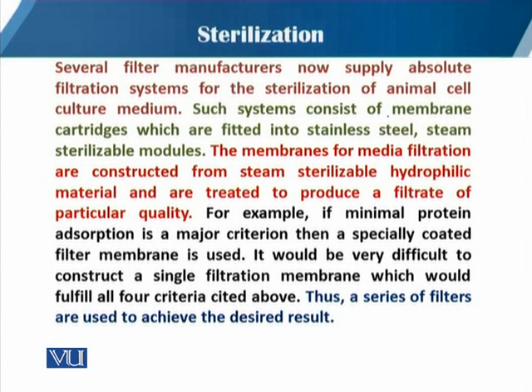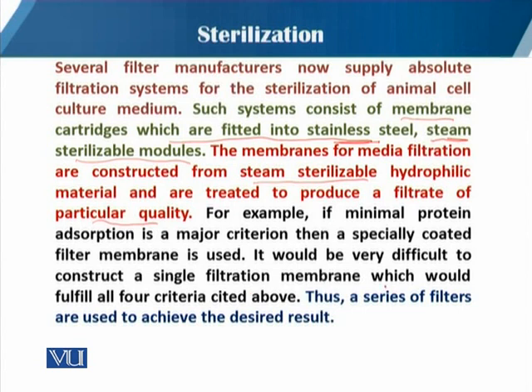Such a system consists of membrane cartridges fitted into stainless steel steam-sterilizable modules. The membranes for medium sterilization are constructed from steam-sterilizable hydrophilic material and are treated to produce a filtrate of particular quality. For example, if minimal protein adsorption is a major criteria, then a specially coated filter membrane is used. It would be very difficult to construct a single filtration membrane that fulfills all four criteria, so a series of filters is used to achieve the desired result.